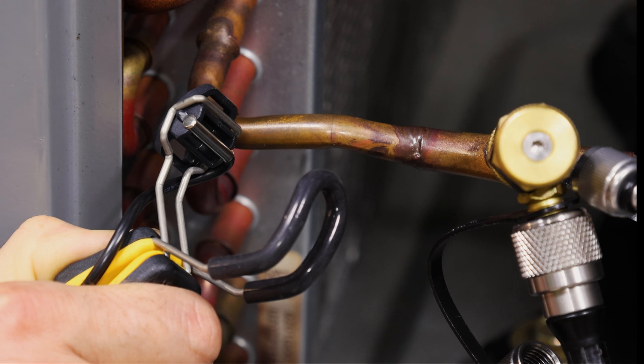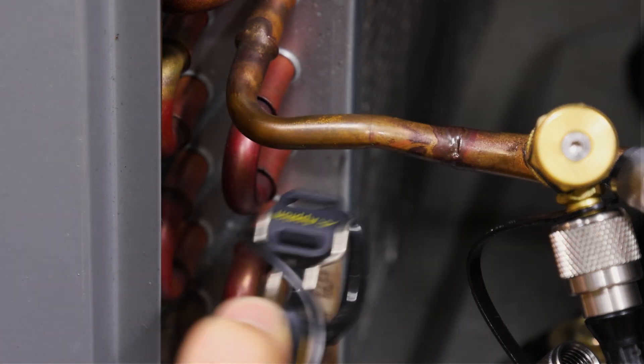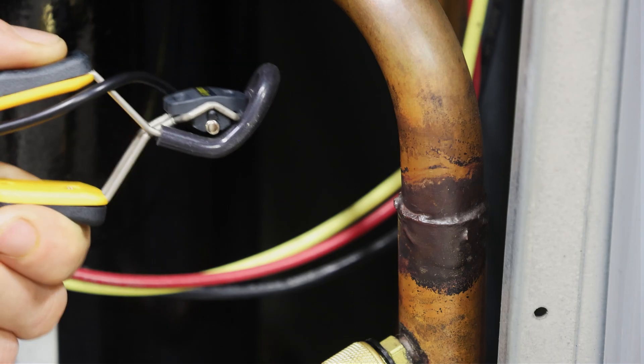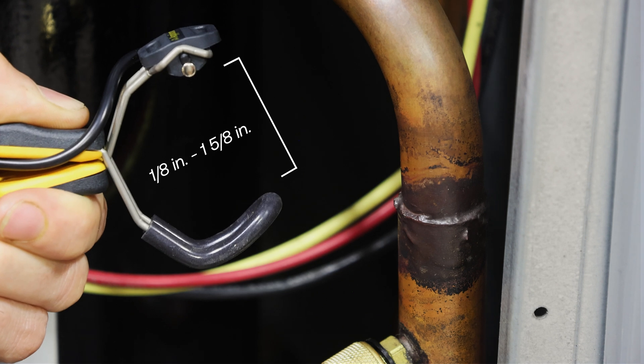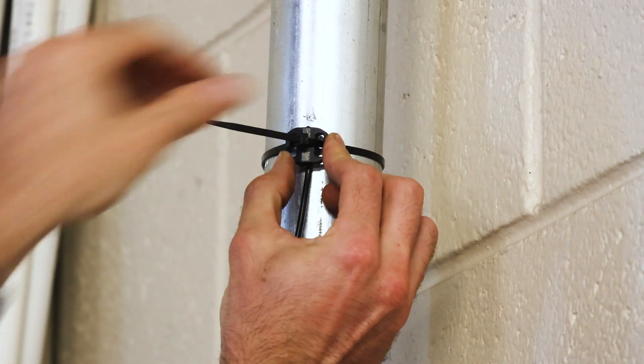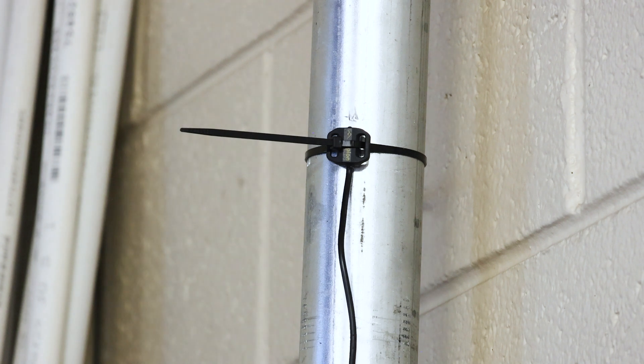The included temperature clamp features minimal thermal mass and a thermally isolated contact sensor that aids in improved response times and highly accurate temperature readings. The temperature clamp fits pipes ranging in diameter from 1/8 inch to 1 5/8 inches. It also has a detachable temperature sensor that makes it highly versatile and compatible with pipes of any size.